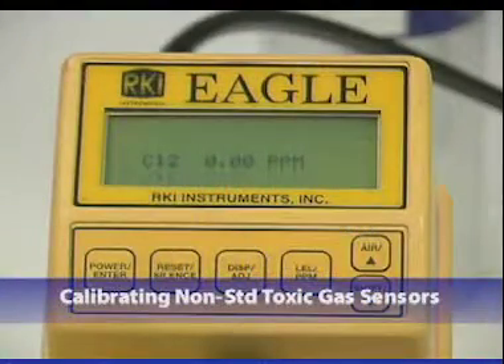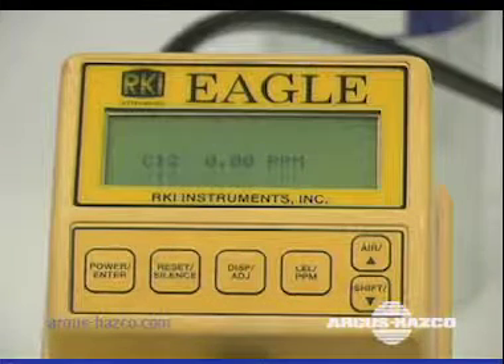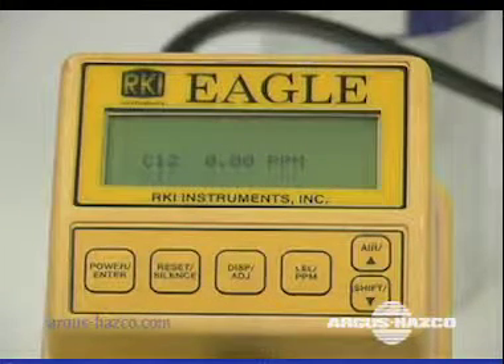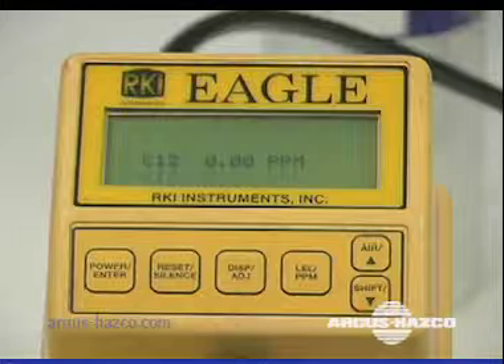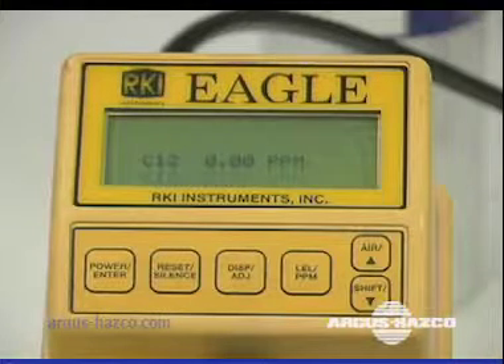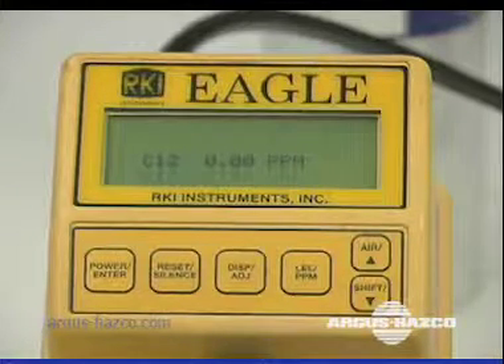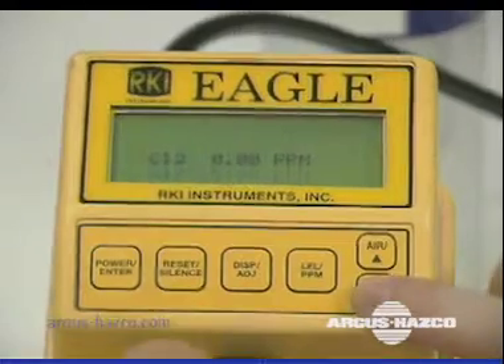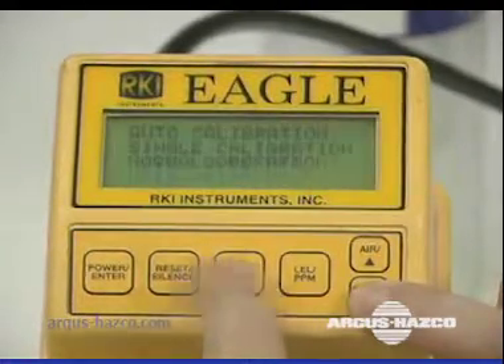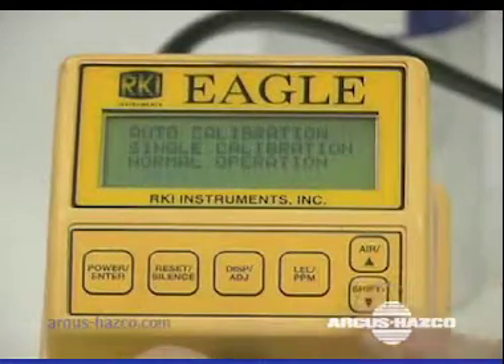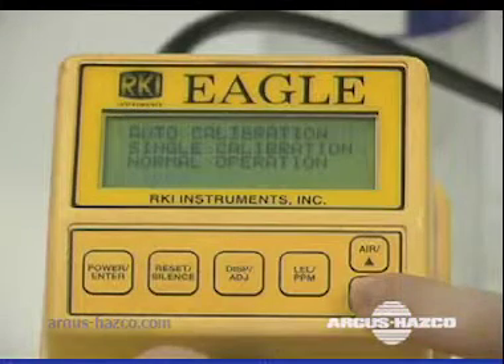Non-standard electrochemical toxic gas sensors are toxic gas sensors other than CO or H2S. The recommended calibration frequency for non-standard toxic sensors is 3 to 6 months. Press the Shift Down button while simultaneously pressing the Display Adjust button to enter the calibration mode. Then select the single calibration option.